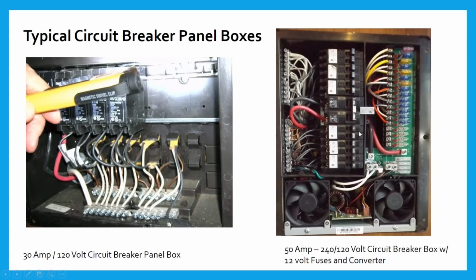Notice where all the black wires are coming off the circuit breakers, the big ones feeding out to all the appliances where we tighten those wires. Down here at the bus bar, all the copper wires are together and all the neutrals are together. We keep these wires totally separate. We do not allow them to get together.